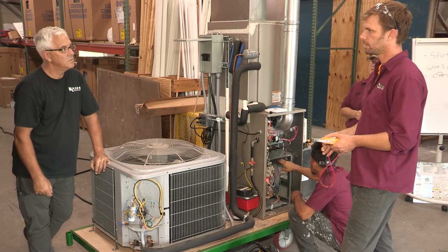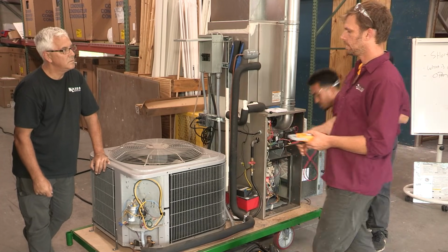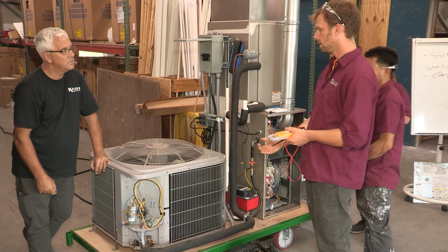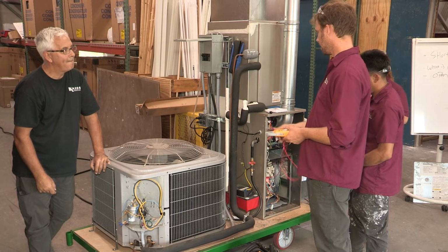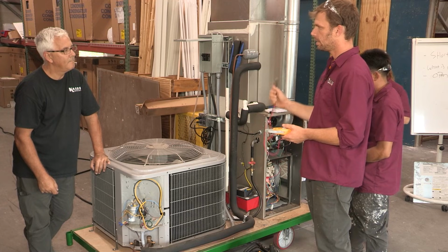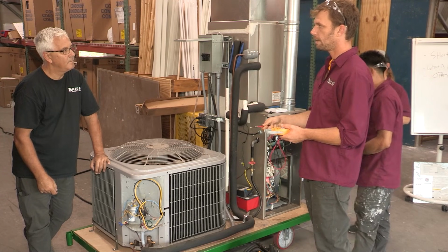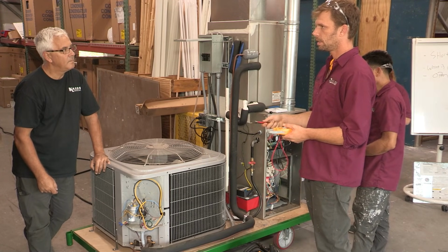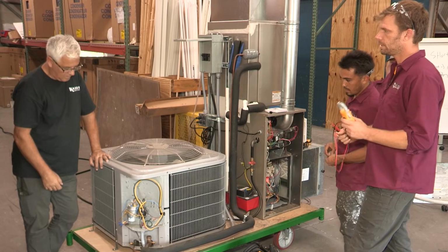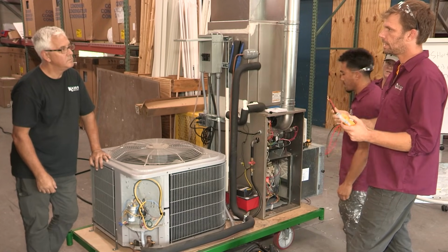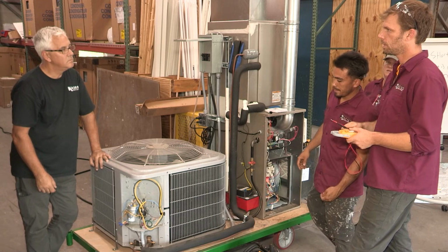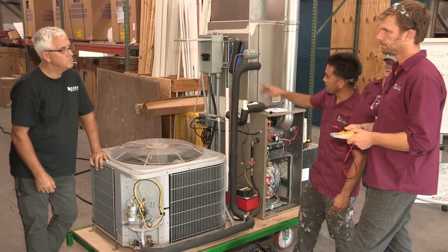That's probably the first thing I would check. So if you were to disconnect your yellow and then take your meter and test between yellow and ground, you should have no path between yellow and ground. So we could ohm between ground and yellow and find out if we have a short to ground somewhere by doing that. All right, we'll turn it off.